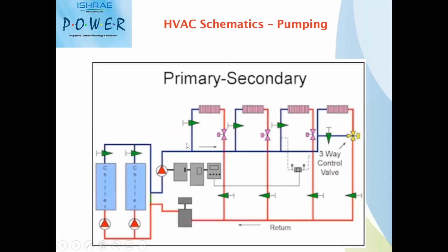And if it is a primary-secondary, up to here you calculate the frictional losses and arrive at the primary head. And flow, of course, is arrived at by the chiller capacities. And when it comes to secondary pumps, the secondary pump heads are calculated based on your farthest AHU pressure drop as well as the complete friction losses. As I told, primary and secondary is always a closed loop system where you don't have to consider any vertical height of the piping or vertical height of the building when you are calculating the heads for the pumps. It is only the frictional losses which come into your calculation when it comes to head calculation for the particular pump.